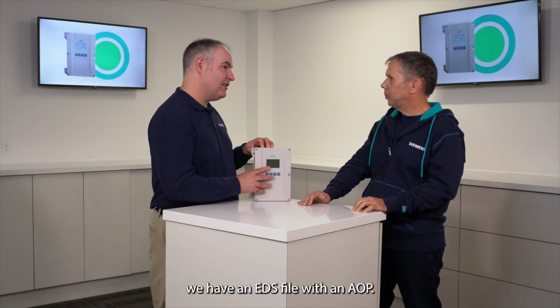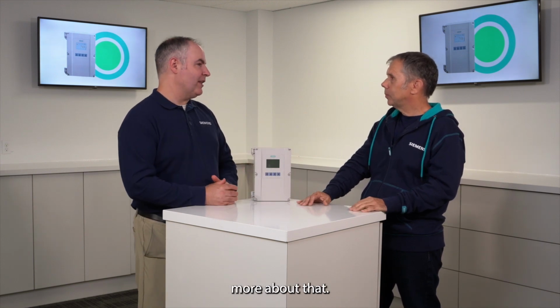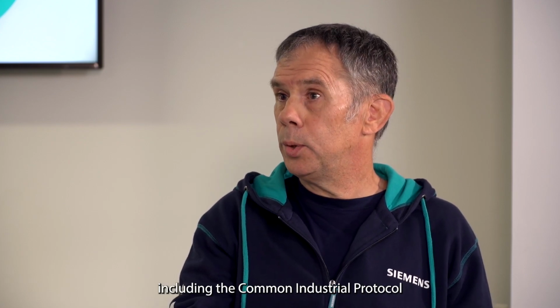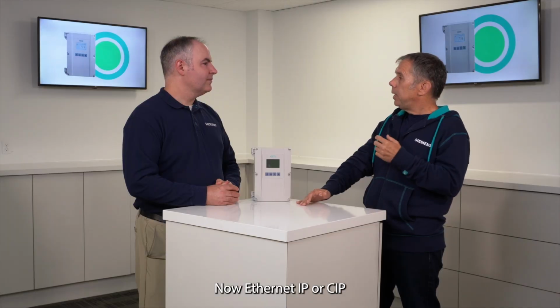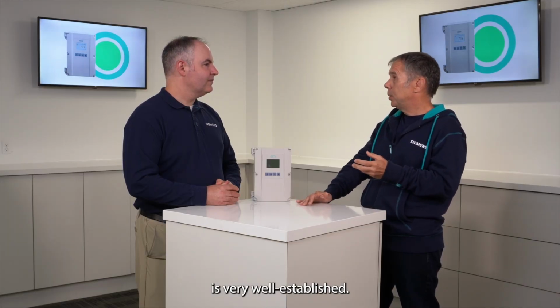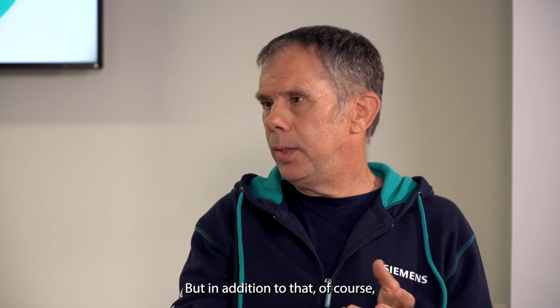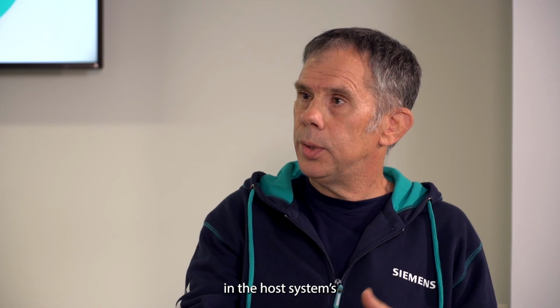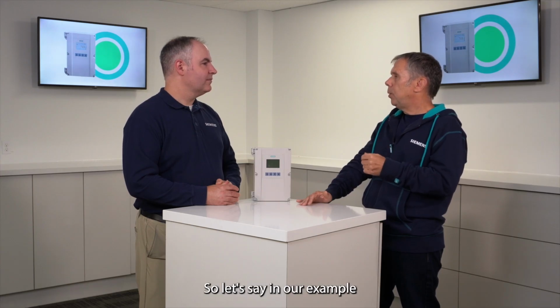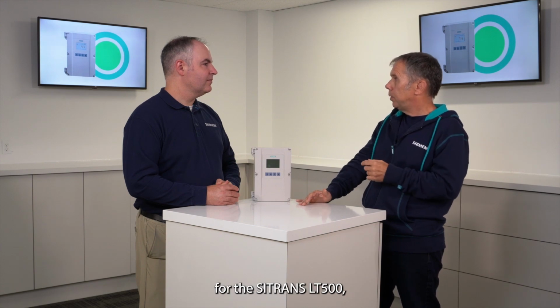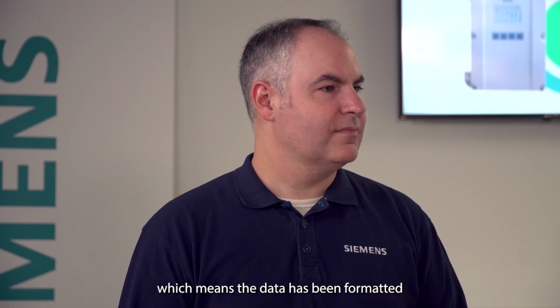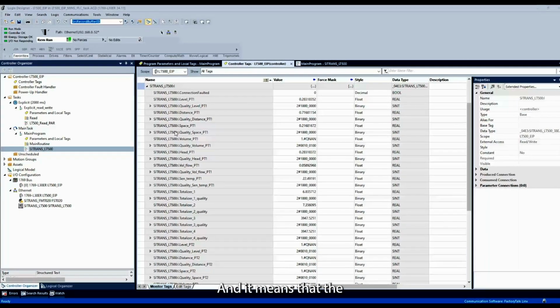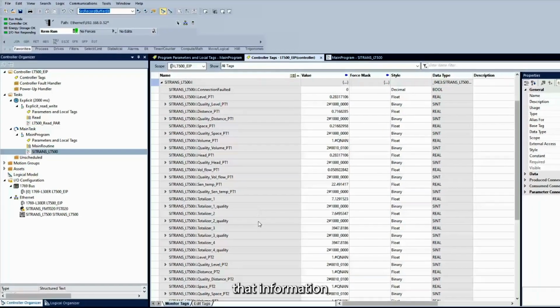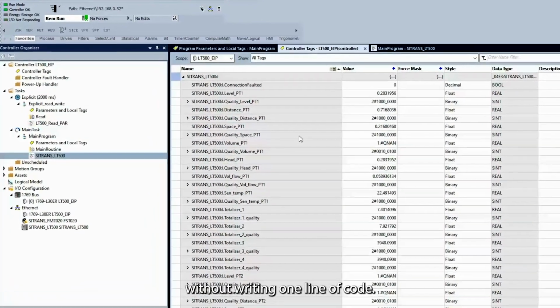Because I understand we have an EDS file with an AOP, and I'd like to understand more about that. Well, Ethernet IP is based on open Ethernet protocols, including the Common Industrial Protocol, or CIP. Now, Ethernet IP or CIP is very well established. It's been around for many, many years. But in addition to that, of course, we have the EDS file. Well, the EDS file is used to configure the device in the host system's configuration software. So let's say in our example for the SITRANS LT500, we have an enhanced EDS file, which means the data has been formatted and tagged, and it means that the user can actually take that information directly into the PLC without writing one line of code.